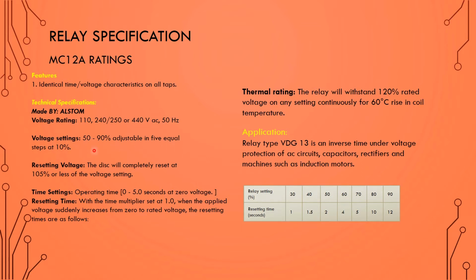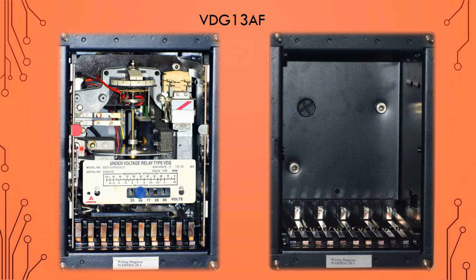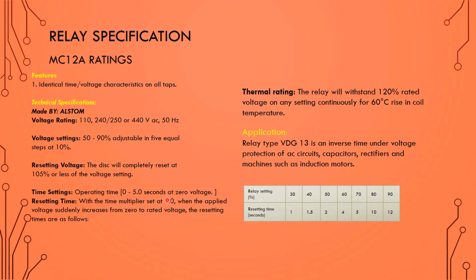Its voltage setting is 50 to 90%, adjustable in 5 equal steps of 10%. As you can see here, 55 and 99. The voltage rating is 110 volt, so the voltage setting starts from 50% of the 110 volt, that is 55, up to 90%, that is 99.